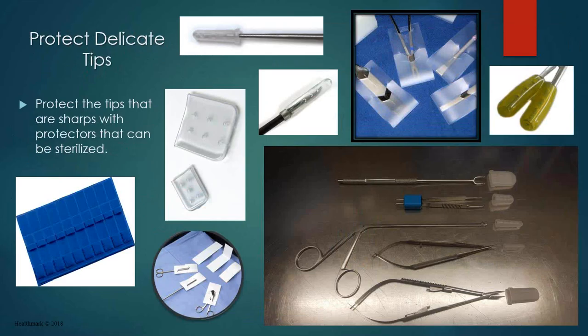Protect sharp tips with protectors that can be sterilized as well. In this slide I try to show a variety of tip protectors that can be used either in peel packs or in the trays. It's really important to know which tip protectors can be used for the right instrument, and you want to always check the manufacturer's IFU to make sure you're using it on the correct instrument or device.